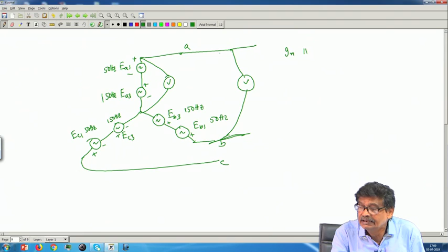Therefore, in the line to line voltage, the third harmonic component will be absent, and this reading will be root 3 times E A 1, because E A 1 is the RMS value. Therefore, in the line to line voltage only 50 hertz will be there, but across each phase the third harmonic component will be there. Got the point?